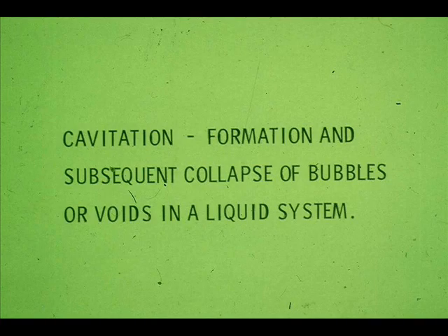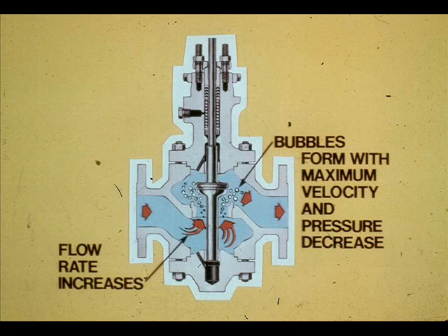We will now discuss several terms used in conjunction with control valves. One such term is cavitation. Cavitation is a formation and subsequent collapse of bubbles or voids in a liquid system. Cavitation occurs in a control valve due to the pressure drop and pressure recovery inside the valve.